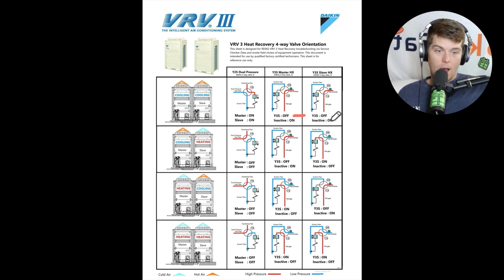This is normal operation. This is low demand or low capacity, low refrigerant charge. So it shifts the four-way valve over on the submodule because it doesn't need the coil, right? There's not enough refrigerant. What am I going to do with this? I'm not doing nothing with this. I can't do nothing with that. Get out of here. So it goes and it shifts the four-way valve over and it only uses the master.